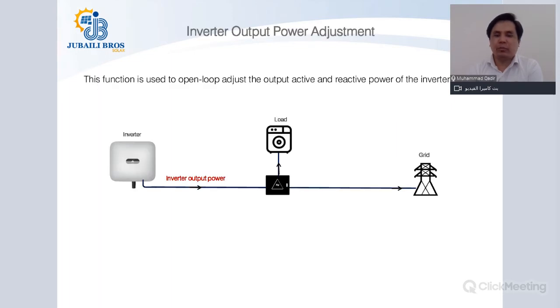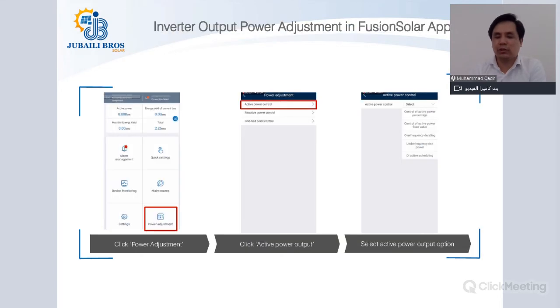Input inverter output power adjustment. Now there is another way that you can control the inverter output, based on what percentage of rated output the inverter should provide, if the inverter is capable of it. So in this scenario there won't be a need for any power meter, as you can see on this screen, because you will just configure the inverter to limit itself to a certain power. So what options do we have in this scenario?